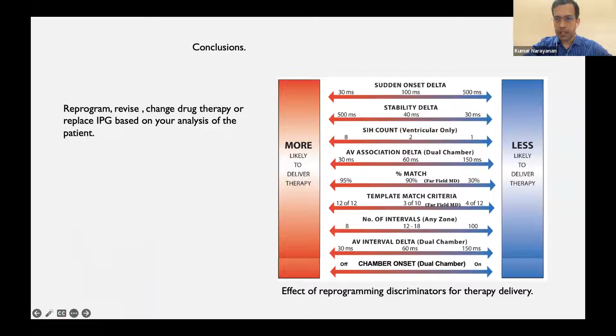You covered some of the fundamentals of how to do this. So to summarize, we can bring out two important points. The first thing, from the point of view of basics, is that ICD sensing is more challenging than pacemaker sensing. That's one important message to get across. Because in pacemaker sensing, it doesn't have to detect tachyarrhythmias. So in ICD sensing, the problem is during VT or VF, the electrograms can be less in amplitude. They can also be very disorganized. So you have to be sensitive enough to detect that, but at the same time, you have to prevent oversensing during normal times. So this is the crux of the challenge as far as ICD sensing is concerned.